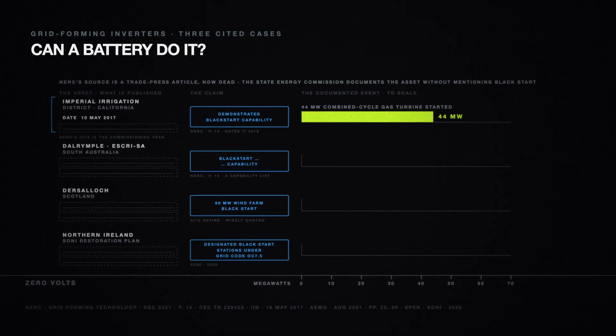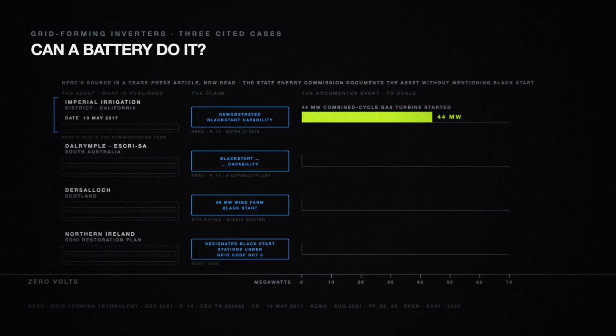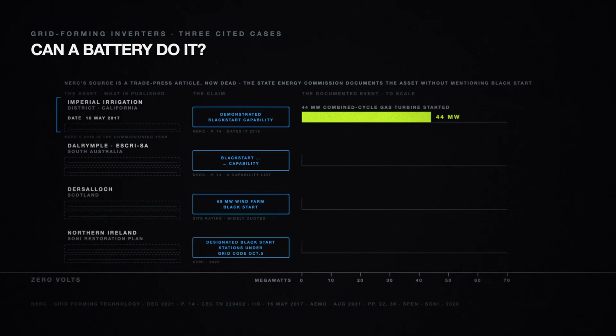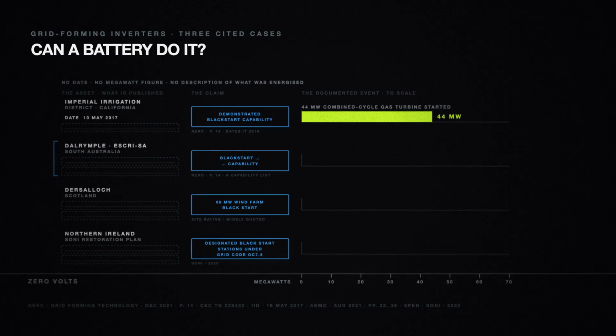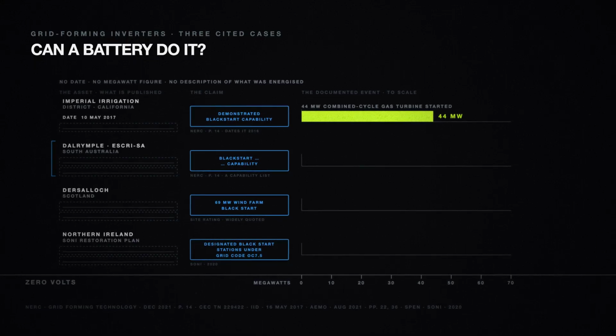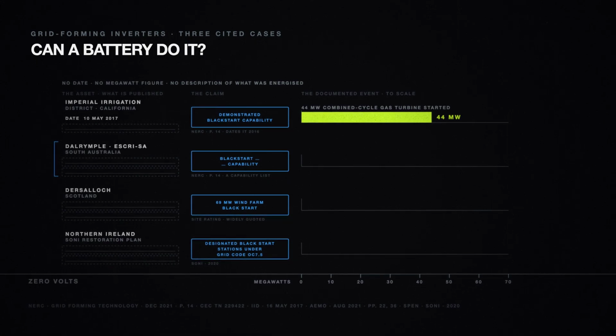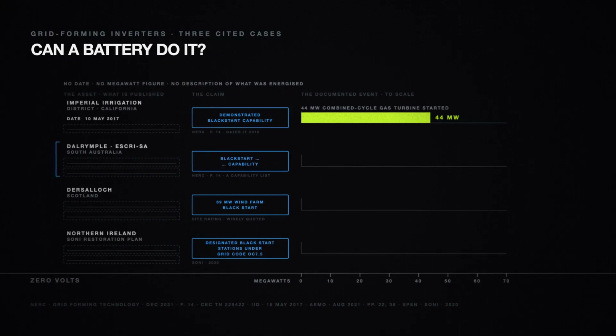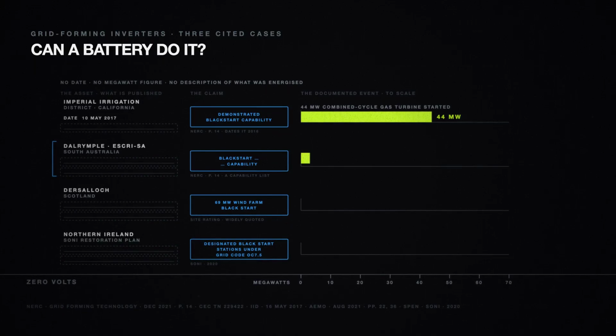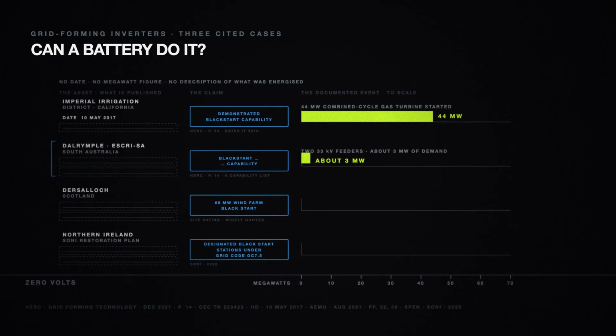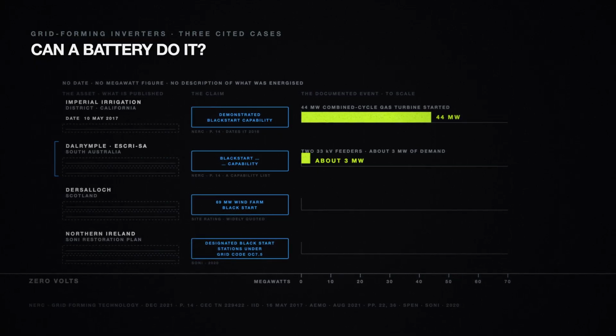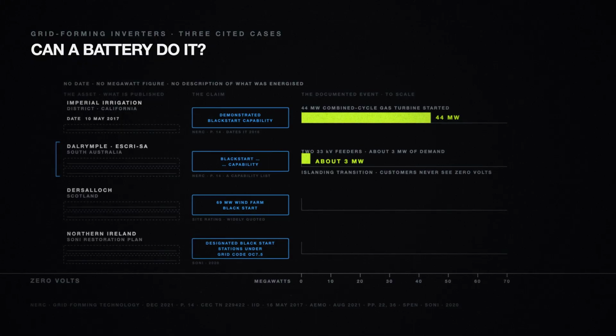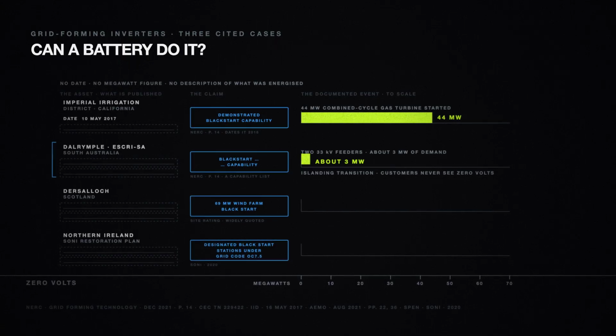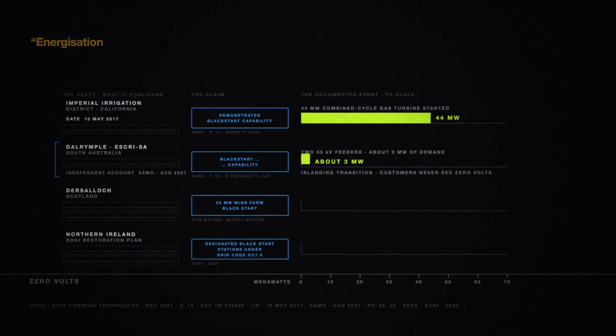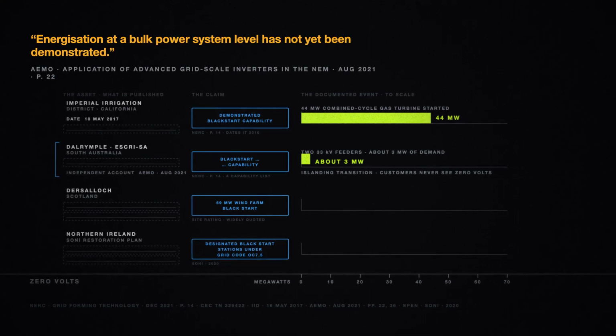The white paper's source is a trade press article now dead, and the State Energy Commission documents the asset without mentioning black start. Second, Dalrymple in South Australia, listed in the same paper as demonstrating black start capability, with no date, no megawatt figure, no description of what was energized. What is documented is 2 33 kilovolt feeders and about 3 megawatts of demand. And Dalrymple's real events are islanding transitions, not black starts. The grid is live, the connection is lost, and customers never see 0 volts. Australia's market operator states the limit. Energization at a bulk power system level has not yet been demonstrated.